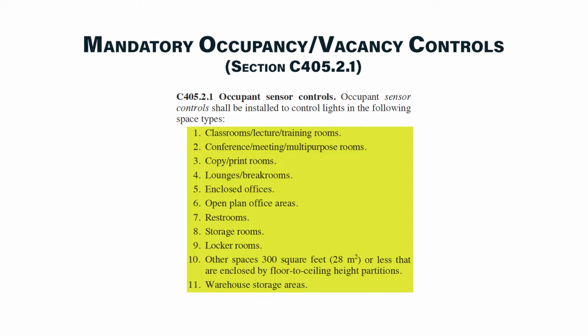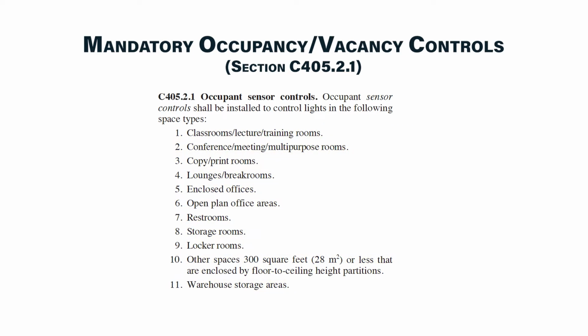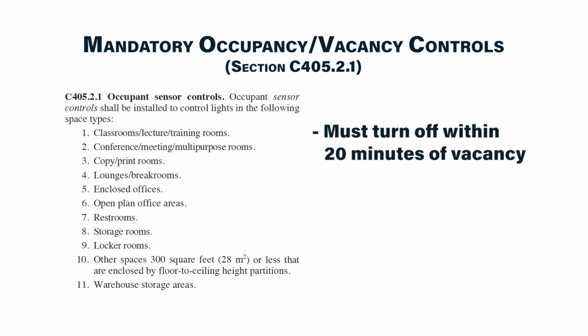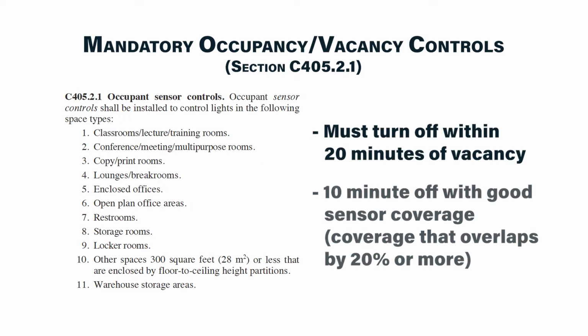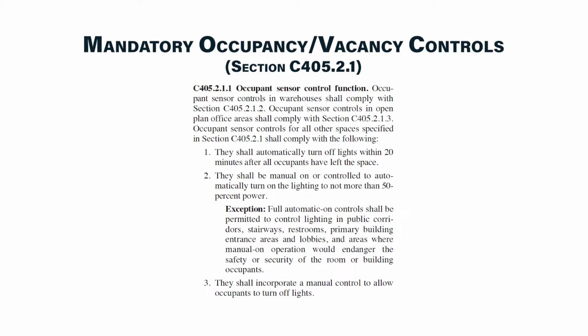11 space types where automatic lighting shutoff is required. Lighting must turn off within 20 minutes of vacancy, but a shorter auto-off in 10 minutes is reasonable with good sensor coverage. The code separately identifies requirements for on control. Automatic on to 100% is permitted in public areas like lobbies, corridors, and restrooms. Remaining spaces are, however, limited to manual on at 100% power or automatic on to 50% power or less. The designer does get to choose vacancy or occupancy on to 50% depending on the best strategy for their application.